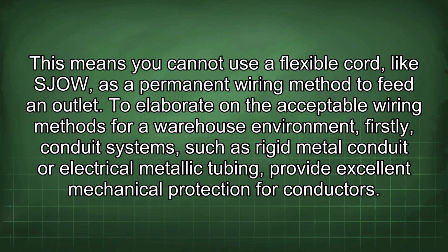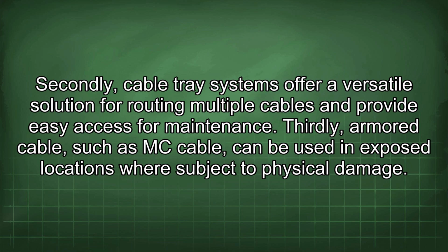an outlet. To elaborate on the acceptable wiring methods for a warehouse environment, firstly, conduit systems such as rigid metal conduit or electrical metallic tubing provide excellent mechanical protection for conductors. Secondly, cable tray systems offer a versatile solution for routing multiple cables and provide easy access for maintenance. Thirdly, armored cable, such as MC cable, can be used in exposed locations where subject to physical damage.